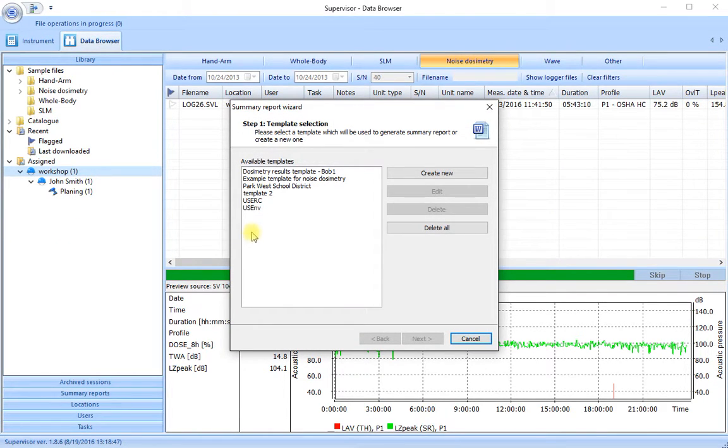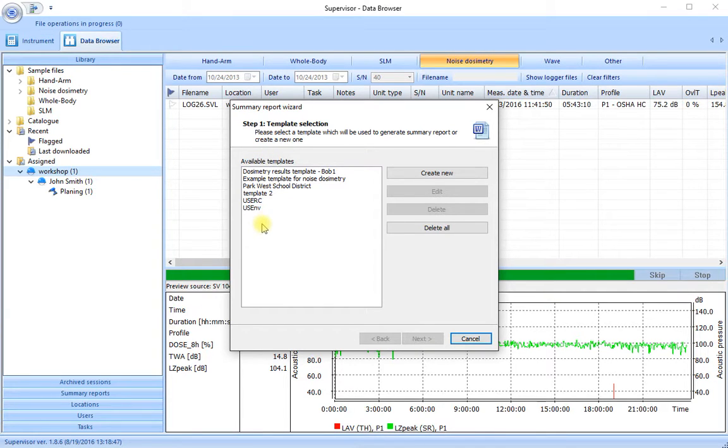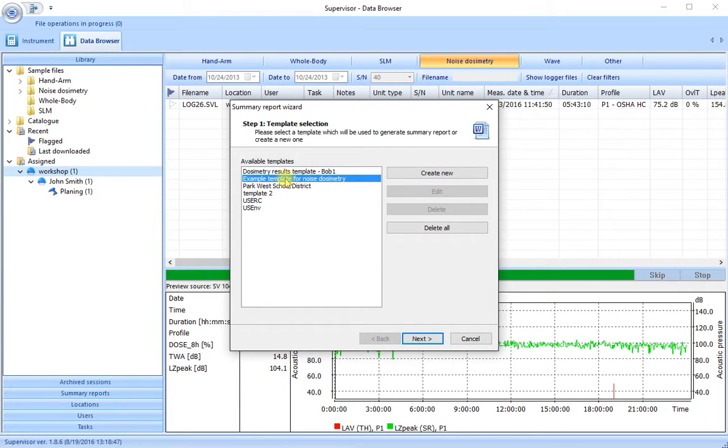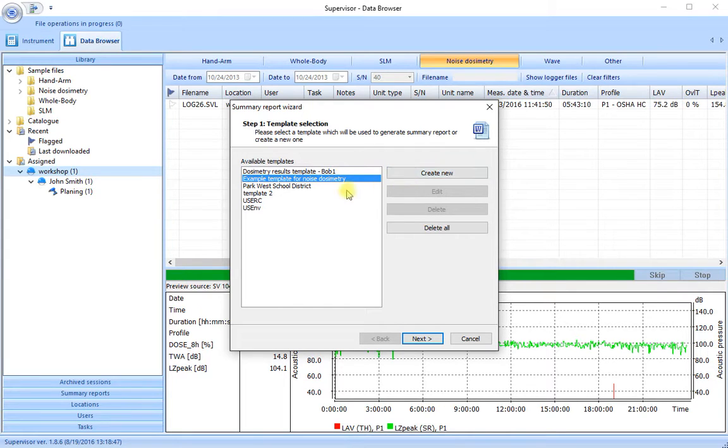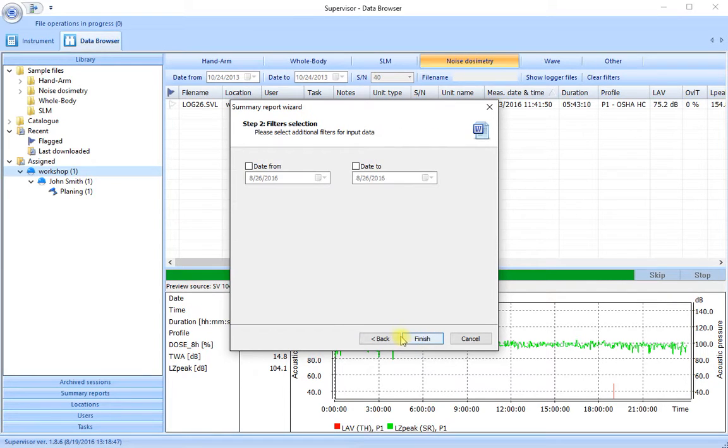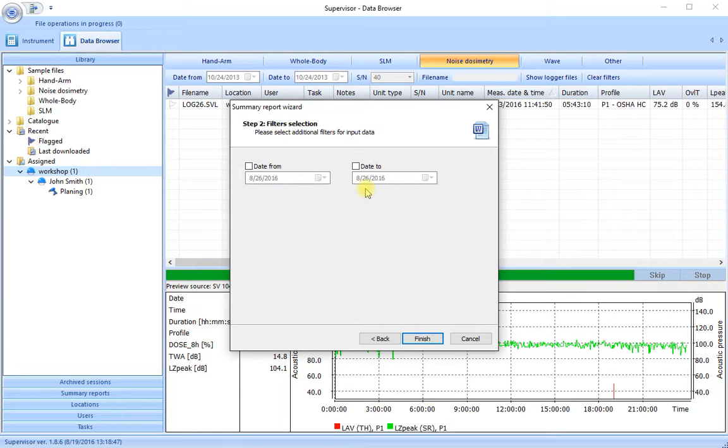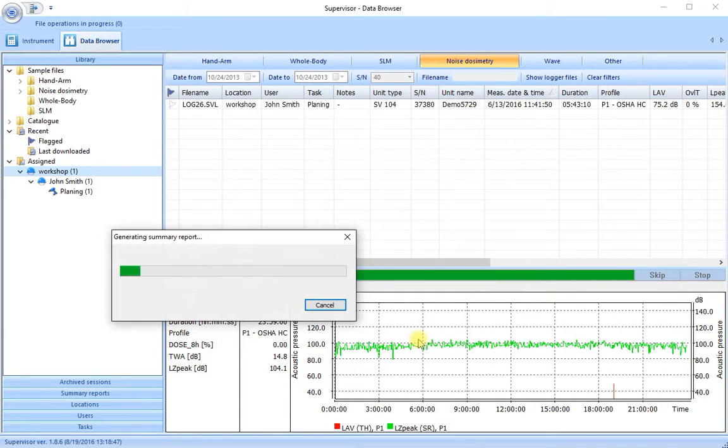So here I have a number of templates that have been created and used. We'll go with the example template for noise dosimetry first. So we select that one from the list. If there wasn't one already available we would create a new one. But we have some here so let's select this one. Let's go to next. If we need to filter for a date range we can do that but we'll leave that for the moment. Let's go to finish.